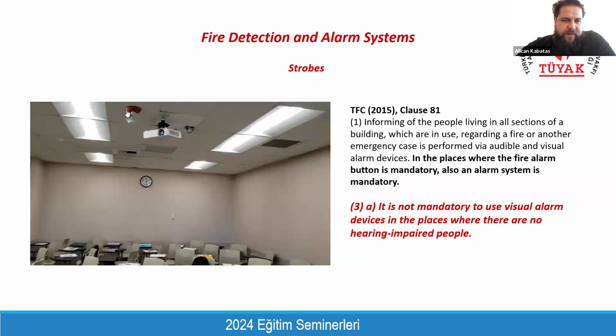And this is one example of a strobe. It can be located either on the ceiling or on the wall, but you need to inform the electrical designer of your preference, your preferred location of the strobes, because the type which is used on the wall is not the same equipment that they use on the ceiling. That's why at the beginning of the design phase, you need to inform electrical designers whether architecturally the strobes are required to be on the ceiling, or on the walls.